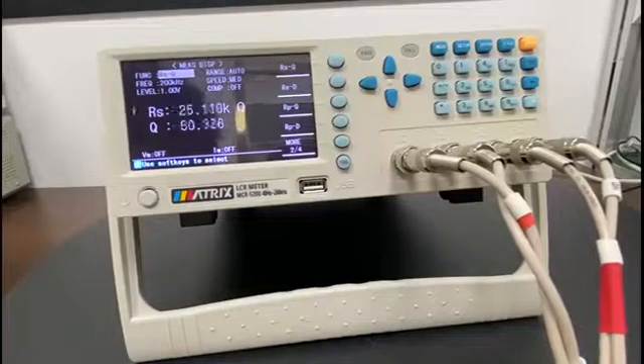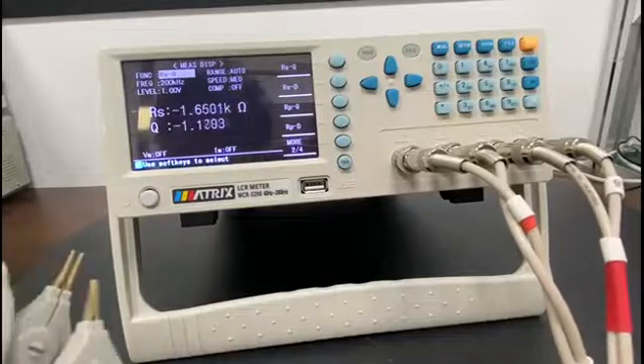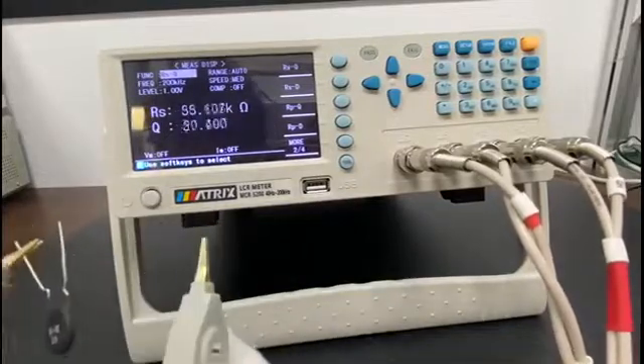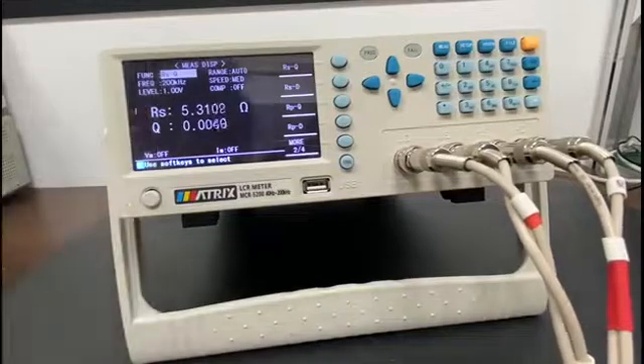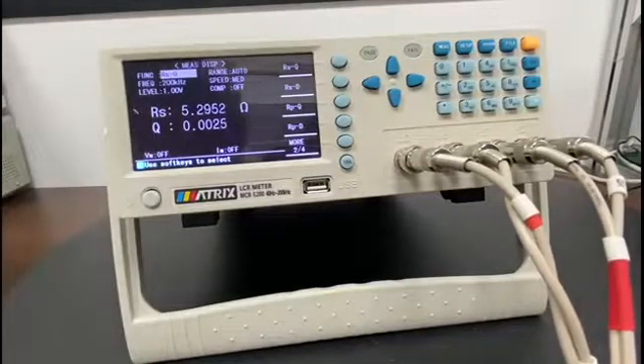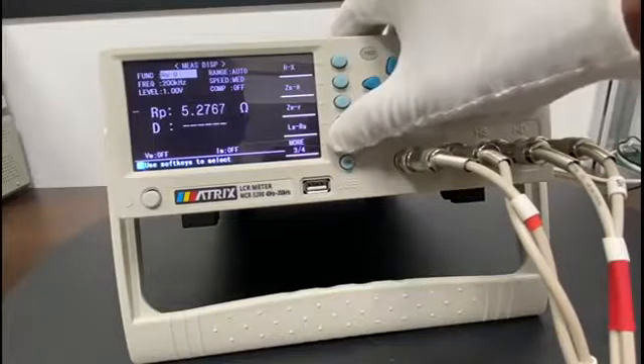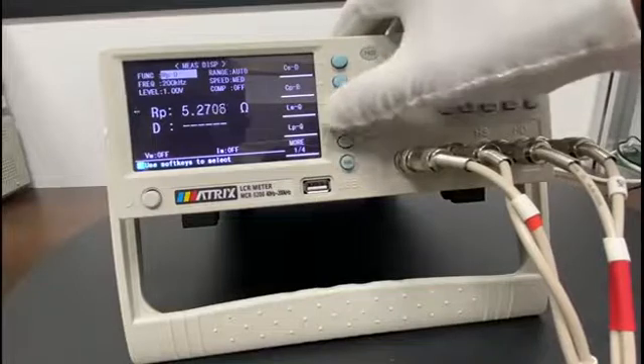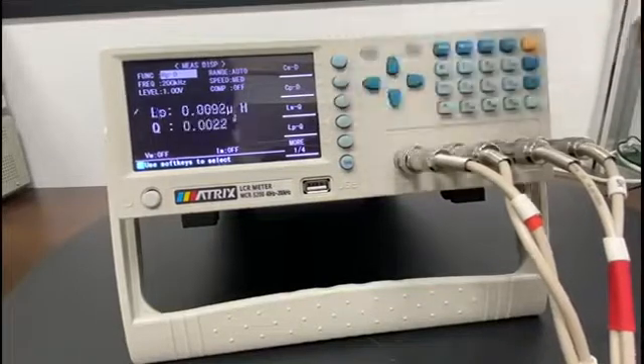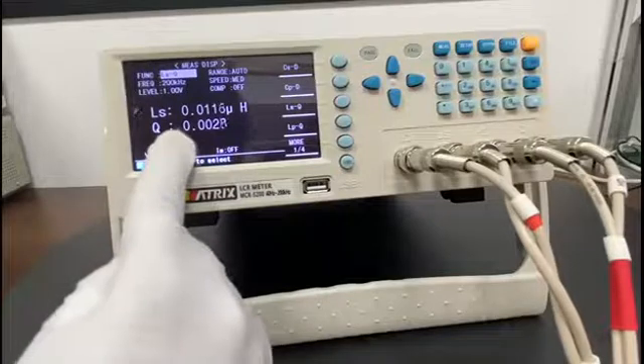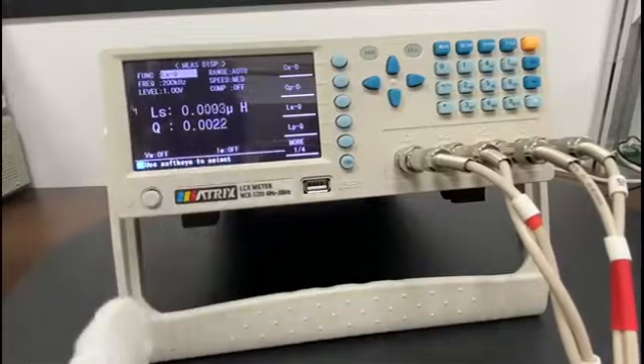Next we will measure one inductor. To measure inductance I will take one inductor and go to LS, inductance in series. Find LS and click this one. We can see the inductance of this inductor is 0.01 microhenries and the Q quality factor is 0.0024.